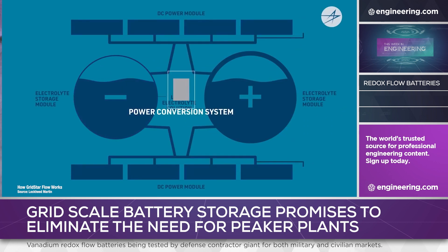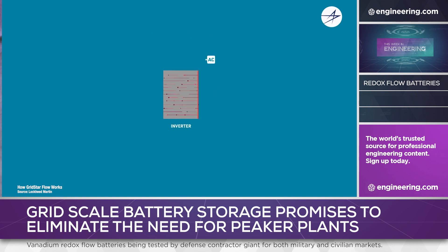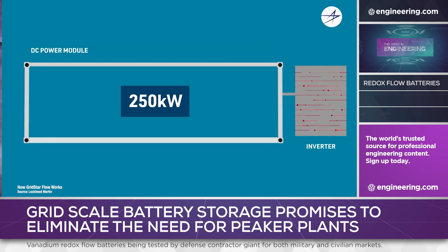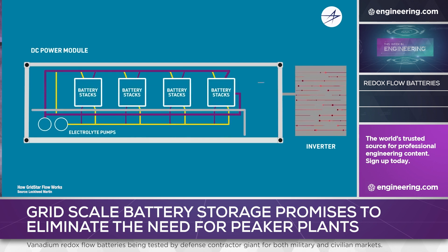Compared to lithium-ion technologies developed for automotive use, flow batteries are large, heavy, require moving parts such as pumps, and have a poor energy-to-volume ratio compared to other battery types. For ground-based energy storage applications, however, weight and volume are rarely a consideration, and the technology has several advantages.